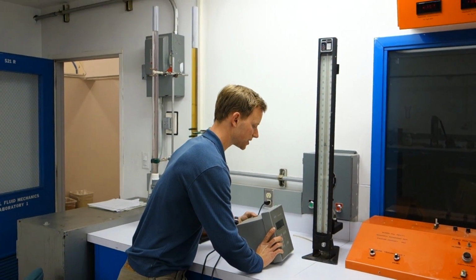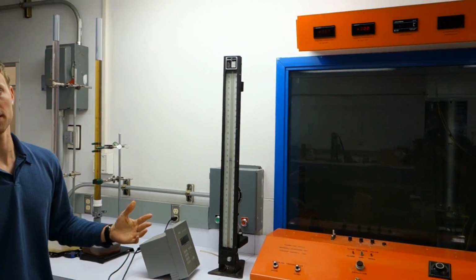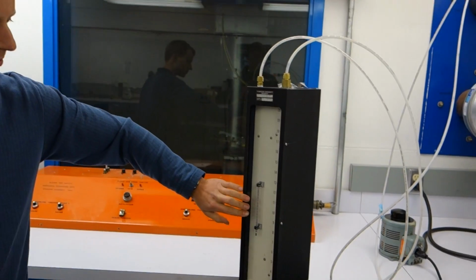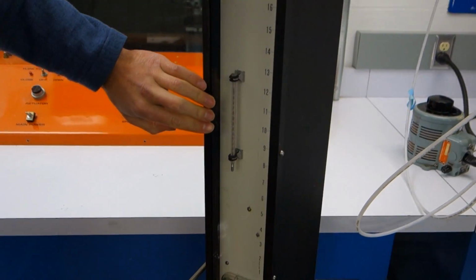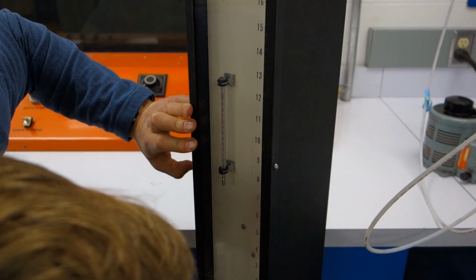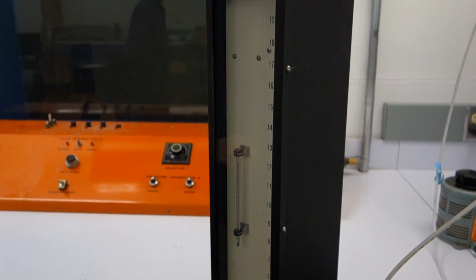In order to calculate H, I'll need to know the density of the medium in which I'm standing, which is air. So I could use a standard value for air, 1.22 kilograms per meter cubed, or I could calculate my own in this room, which is preferable. To do that, we'll use the ideal gas law. So we'll need temperature, and we'll need R for air, which is 0.287 kilojoules per kilogram Kelvin. And to find temperature, we'll use the thermometer in this barometer, this pressure gauge right here. So it's reading 20 C.